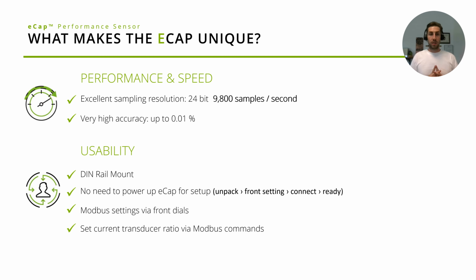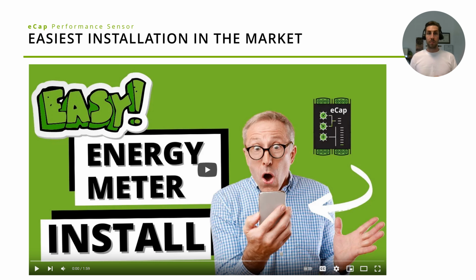Another nice feature: once the product is installed and wired up to a PLC, you don't necessarily need software to tell it your current transducer ratios. You can do that through Modbus commands and your PLC, saving you some power-up and testing time as well.